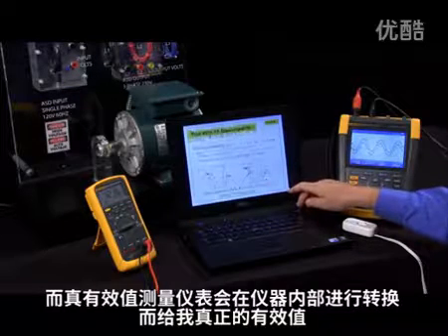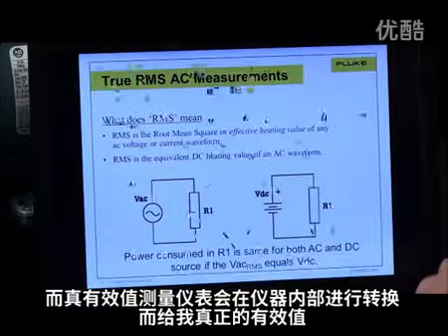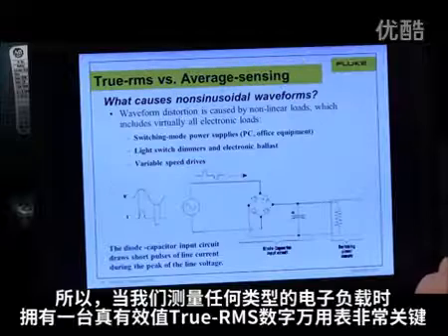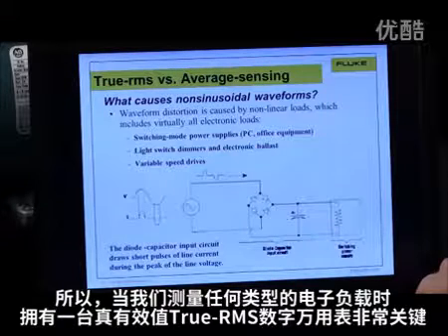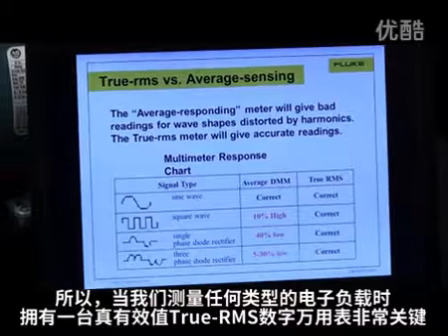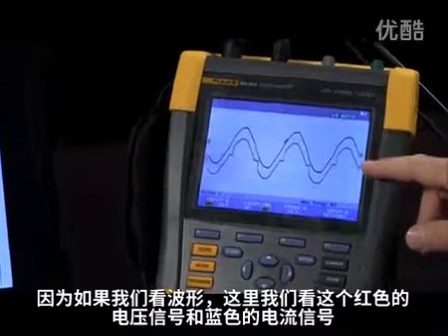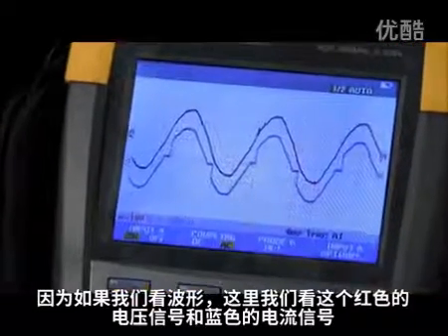A true RMS meter actually does this conversion inside the meter and gives us the true RMS reading. So when we're working with any type of electronic load, it's important to have a true RMS meter. If we look over at the oscilloscope, here I'm showing the voltage signal in red and the current signal in blue.